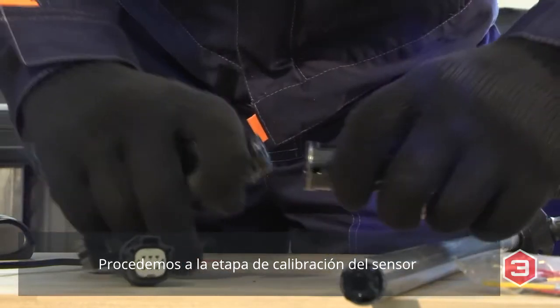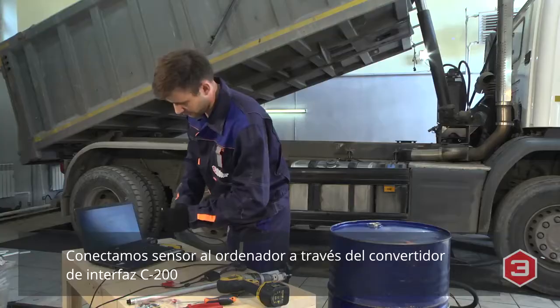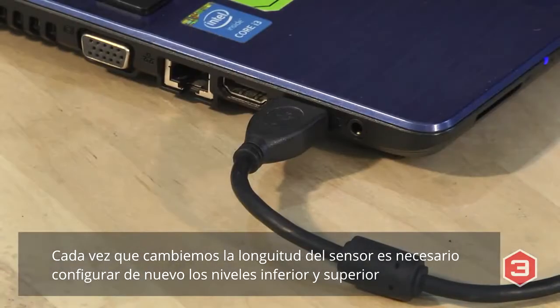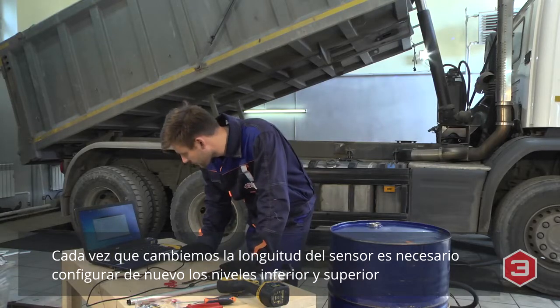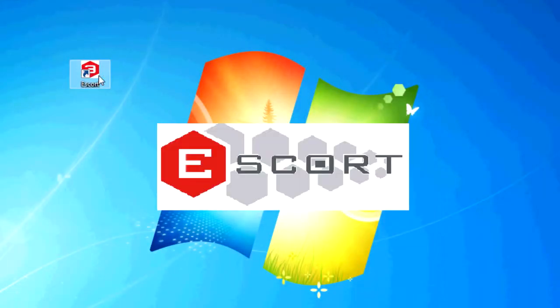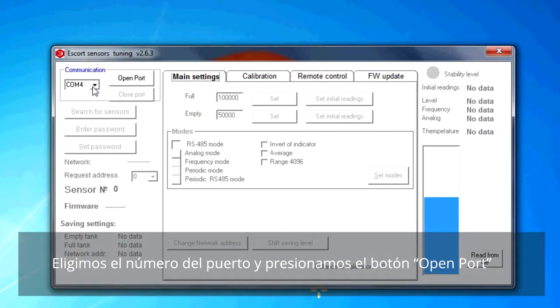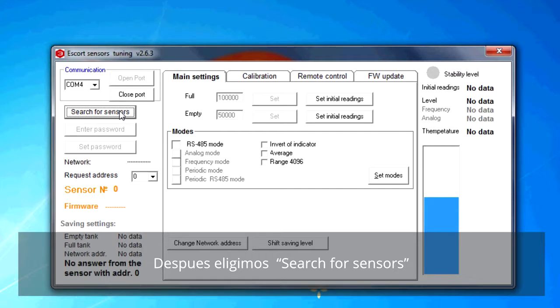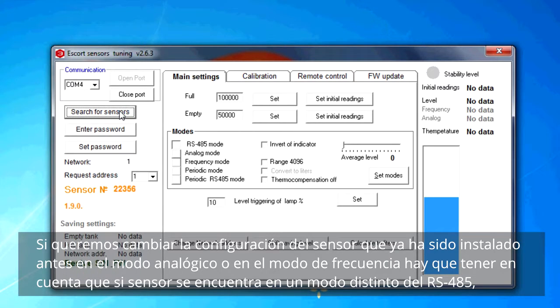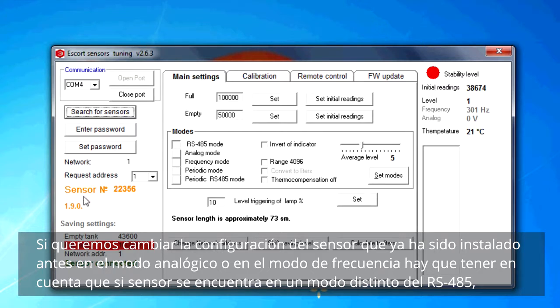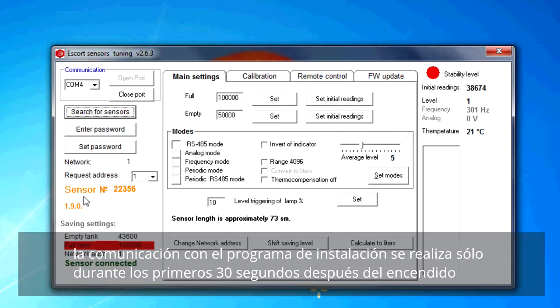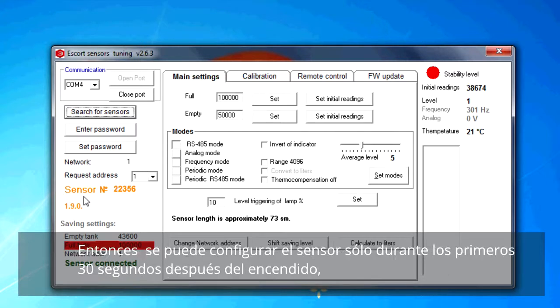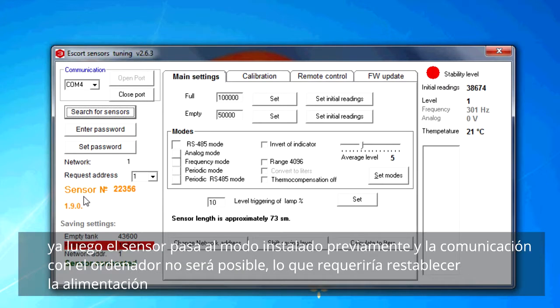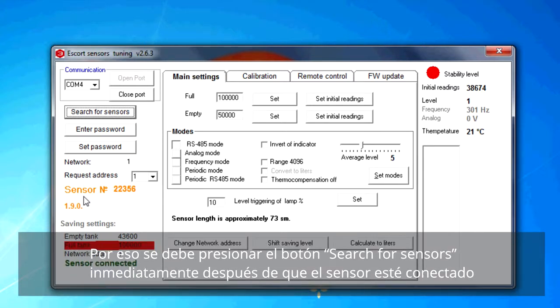The fuel sensor calibration. Connect the sensor to the computer using the C200 interface converter. Upper and lower levels have to be set after each length measurement. Choose the COM port number, then click the Open Port button, then press Search for sensors. If the sensor is in a mode other than RS485, it can connect with the TD500 software only during the first 30 seconds after it is turned on. Then it will roll back to the previous mode. Connection with the computer will be unavailable and a power reset will be required. Press Search for sensors right after the sensor is connected.